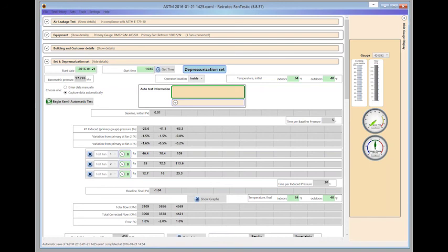And hook up the gauges correctly according to our tubing diagrams, which means the red tube always passes through the red panel from inside to outside or outside to inside. It's a red tube that goes across the building. As long as you do that, it will always tell you whether you are pressurizing or depressurizing.